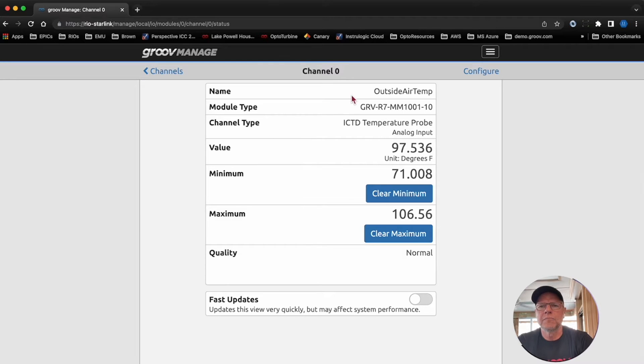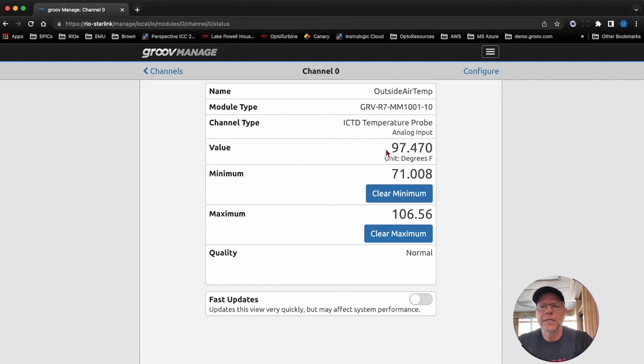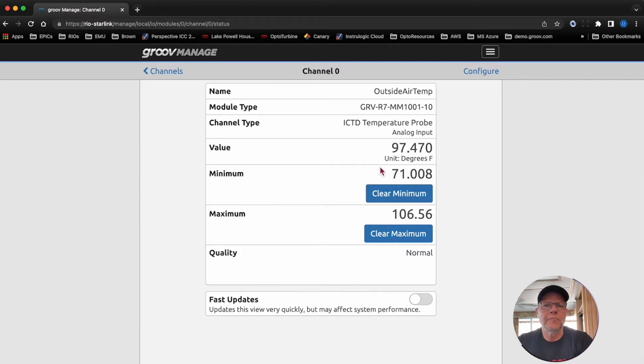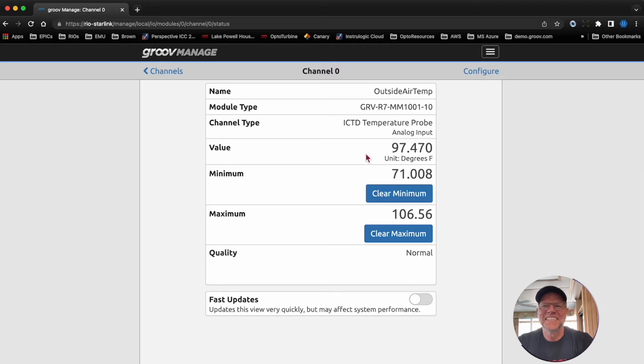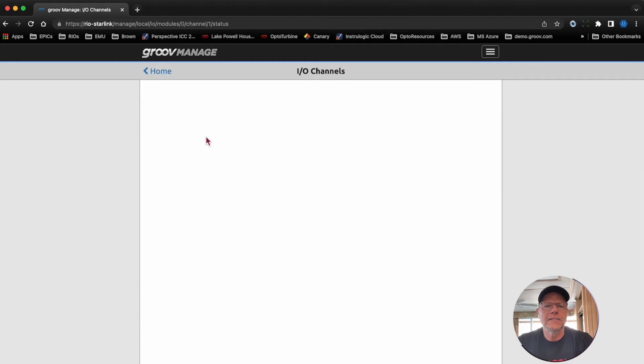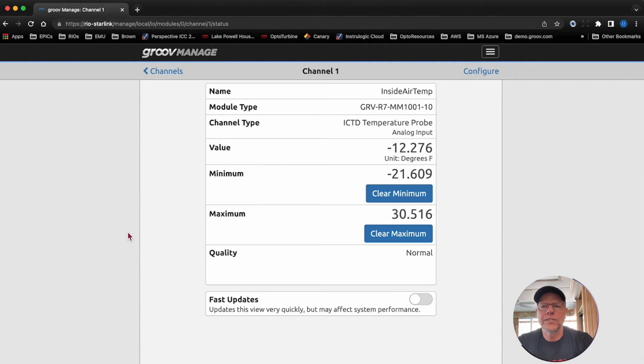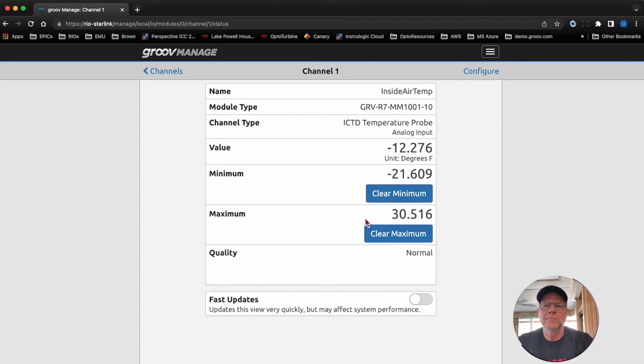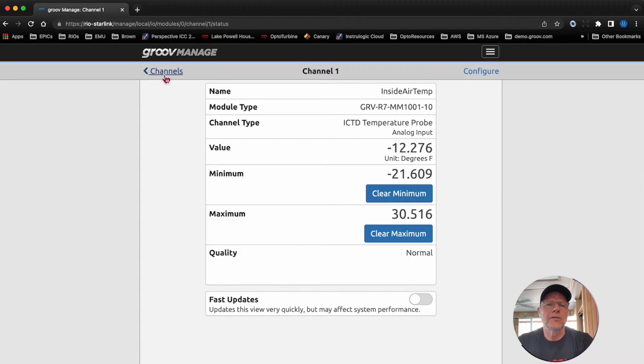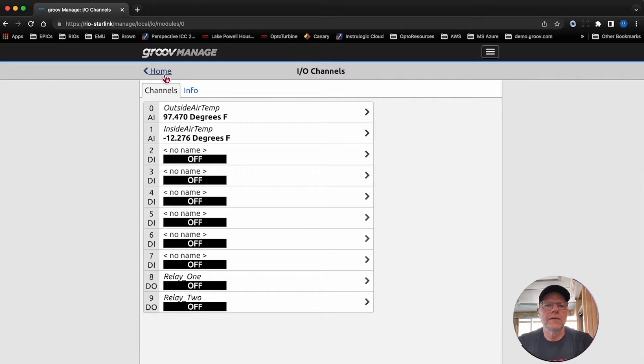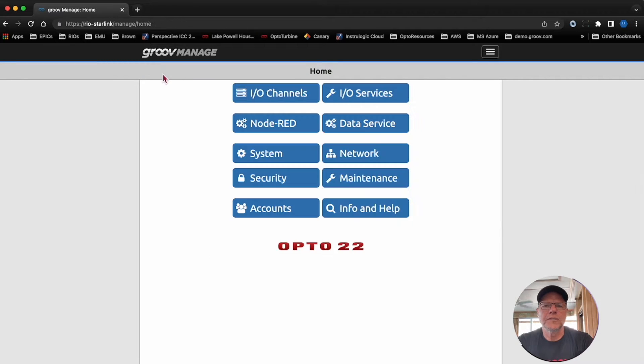First things first is the I/O channels. You can see there I've got my channel name and it's an ICTD temperature probe. Here I've been capturing both the min and max values, so it's gotten up to 106, as low as 71, currently it is 97. Same thing here with my freezer, it's gotten down to minus 21, up to 30 degrees, which is all good. No alarms there, everything has been good.